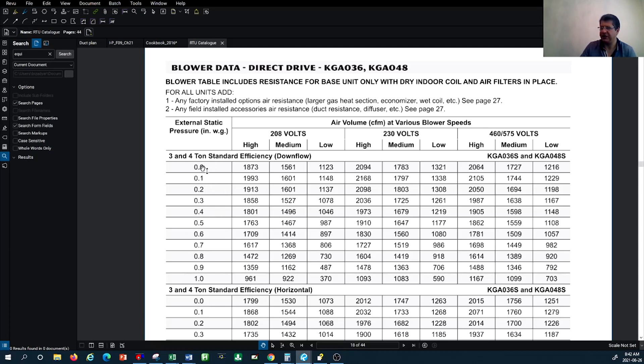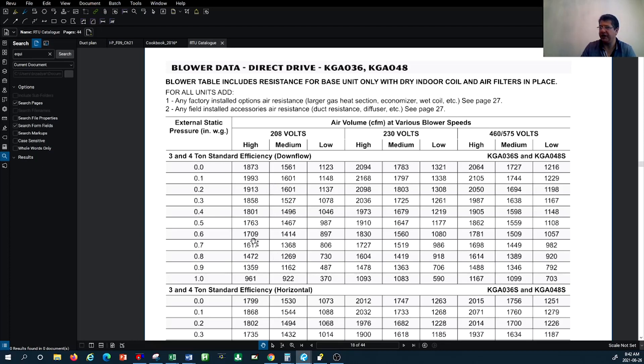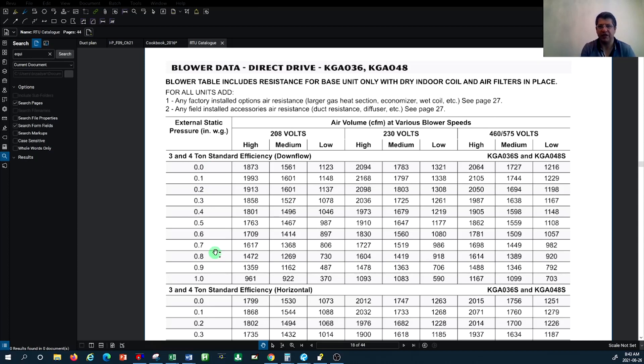At different static pressures, starting from zero — meaning no resistance in the duct work — all the way to one inch of water column resistance, you can see what air volume can be circulated through this fan. The higher the static pressure, the lower the air circulation. When we size our duct system we want to remain within the boundary of our fan motor's static pressure capacity for delivering a certain amount of air.